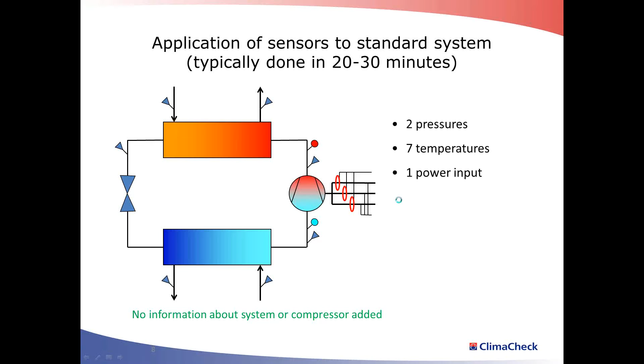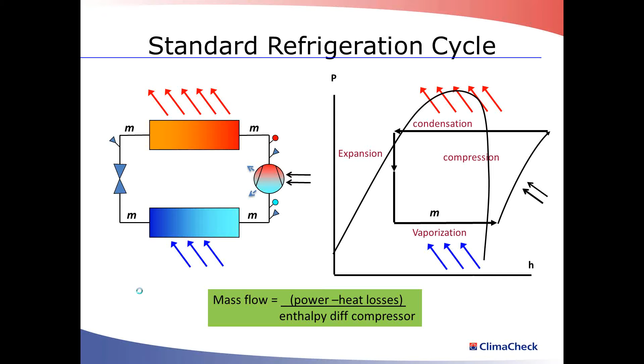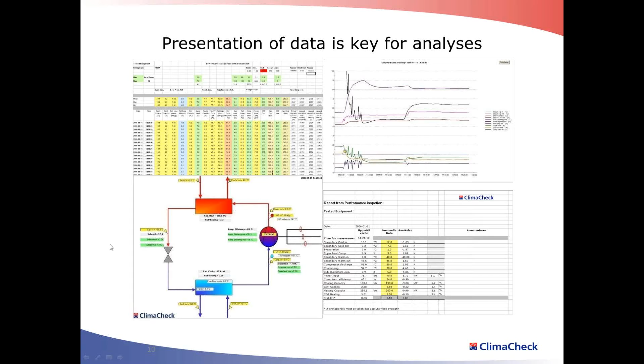When we have this information and the refrigerant properties, we can calculate the enthalpies of the system. This gives us the heating capacity, cooling capacity and the COP of the system. The trick is that we can use the compressor as a mass flow meter when we know the power input and the enthalpy difference of the compressor. Then we also know the mass flow of refrigerant, and that gives us the possibility to calculate the capacity. Then it becomes a question of showing this data for the refrigeration and air conditioning expert or the technician to be able to interpret it and see what could be improved and what is not as it is intended to be.